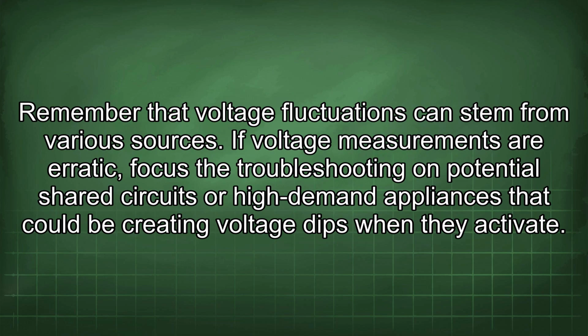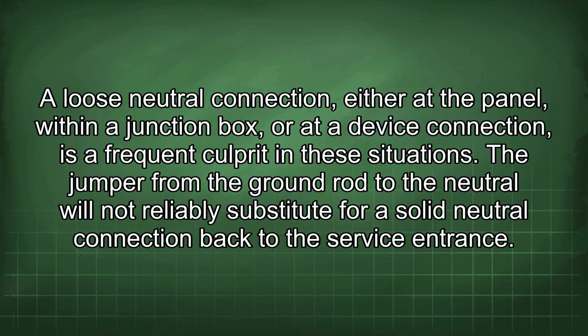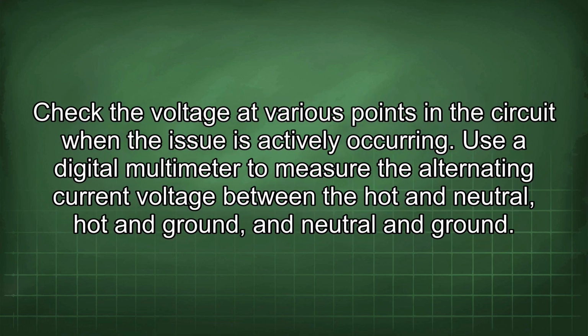Remember that voltage fluctuations can stem from various sources. If voltage measurements are erratic, focus the troubleshooting on potential shared circuits or high-demand appliances that could be creating voltage dips when they activate. A loose neutral connection, either at the panel, within a junction box, or at a device connection, is a frequent culprit in these situations. A jumper from the ground rod to the neutral will not reliably substitute for a solid neutral connection back to the service entrance. Check the voltage at various points in the circuit when the issue is actively occurring.